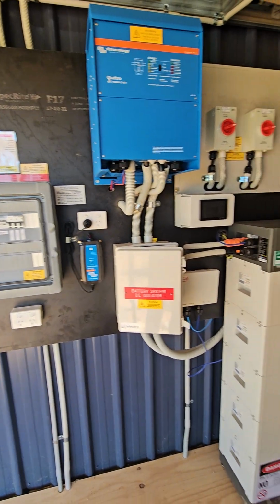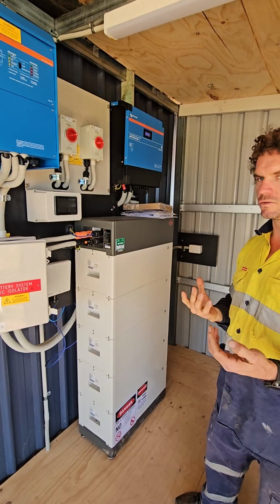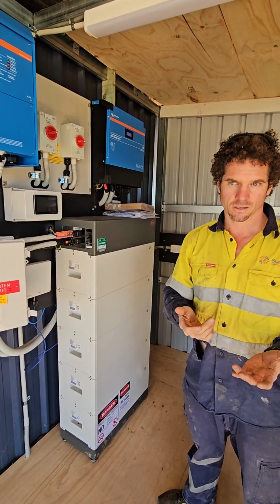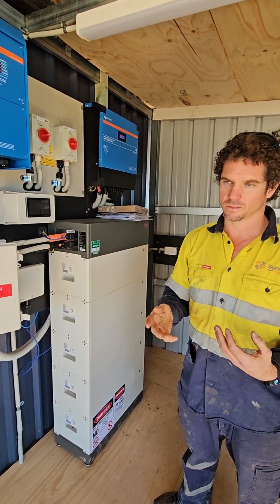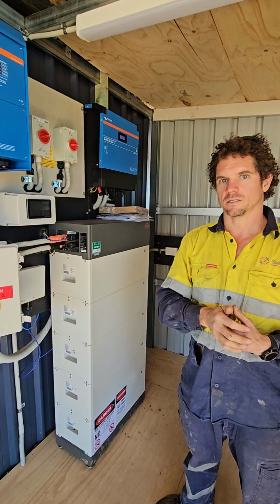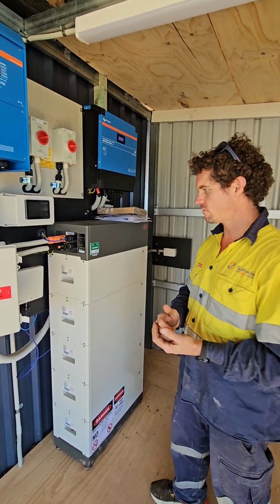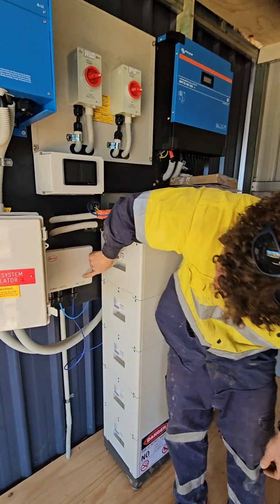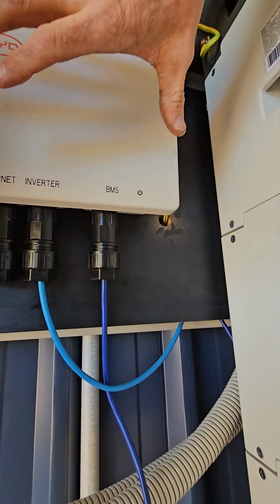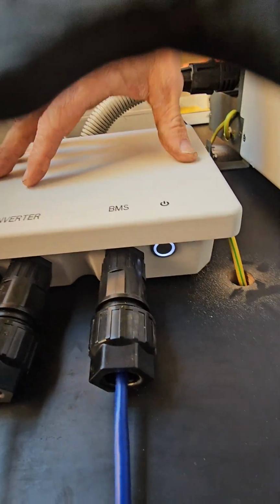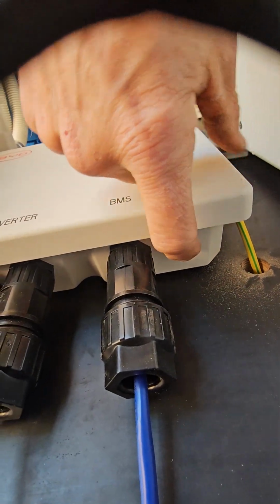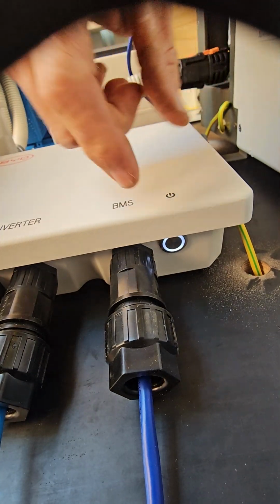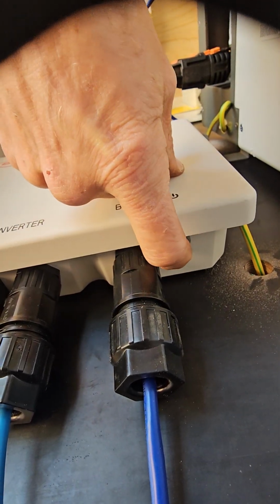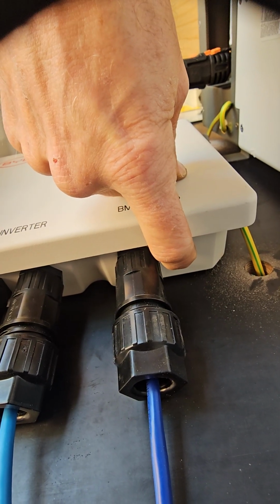There is one more point if you need to do a further isolation, but that's more if you need to reset the whole system, where you actually turn off the battery as well. To turn off the battery, there's a button on the BMU here - this is your battery communication unit. There's a little button under here with the power symbol on the front, and you press and hold that for about 5 seconds.